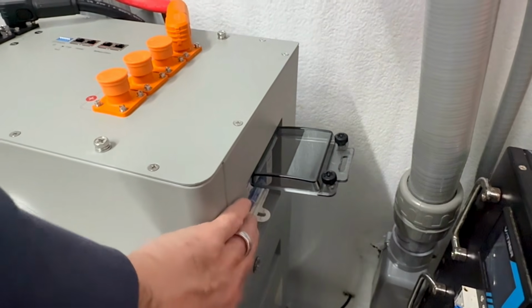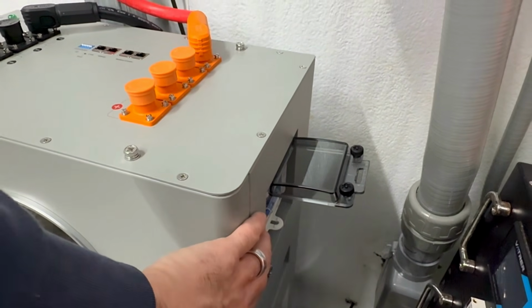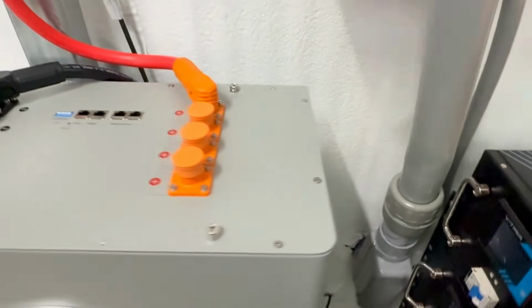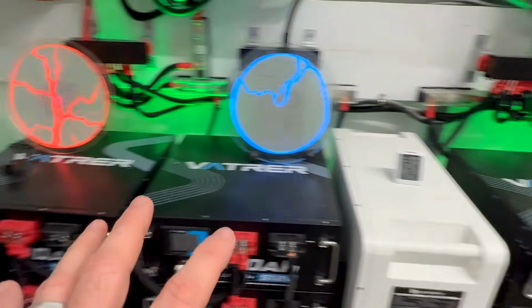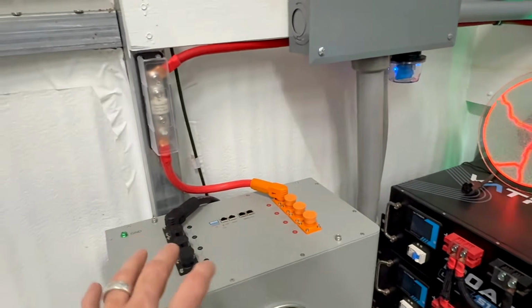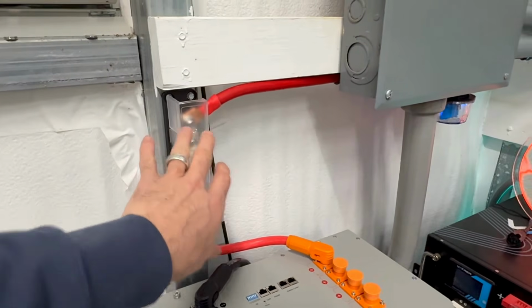Now, I do have this fuse, and you may look at this and say, wait a second, it already has a breaker on the side. Having that circuit breaker is enough, and if you have a circuit breaker on each of your batteries, you are fine. However, if you're setting up a very large array of batteries all in parallel, you may want to put fuses for each string.